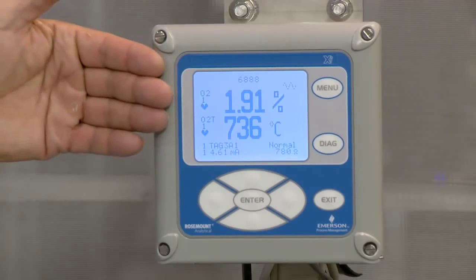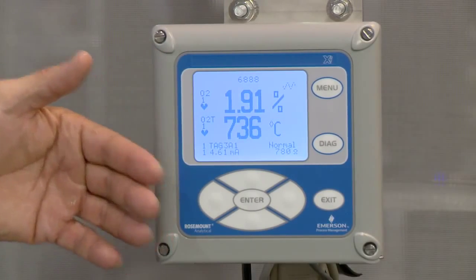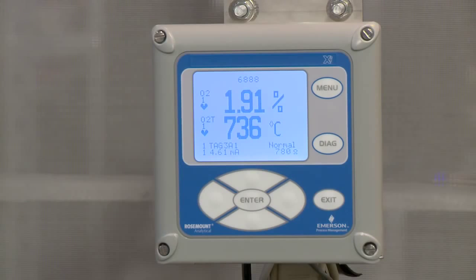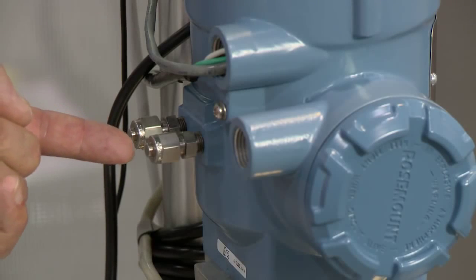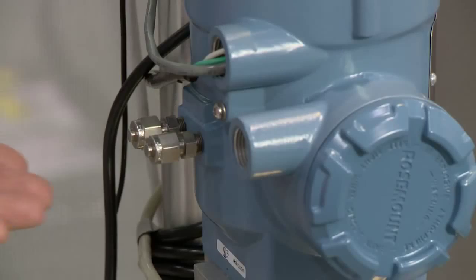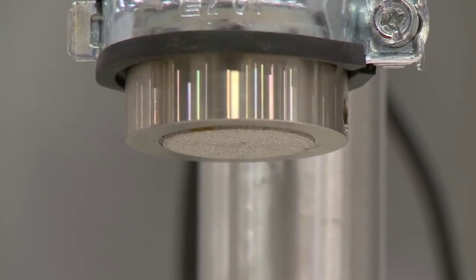This instrument offers a feature called Calibration Recommended Diagnostic. On an online basis, it determines when it needs to be calibrated, so it eliminates many unnecessary calibrations that you may be conducting today. Additionally, this new instrument has calibration solenoids and electronics right inside the head of the probe. So when the Calibration Recommended Diagnostic determines that it needs to be calibrated, your gas bottles are hooked up to here continuously, and the solenoids will pop and gases will be introduced to the sensor, all online while the furnace is still operating. In addition to integral AutoCal, this instrument offers several other unique features, such as plug diffuser.